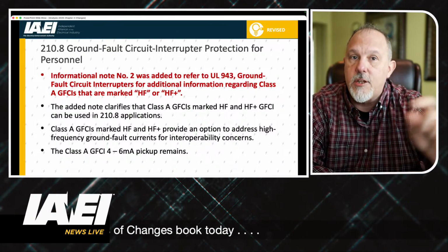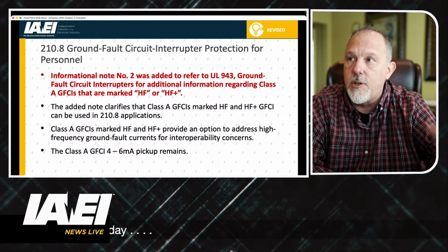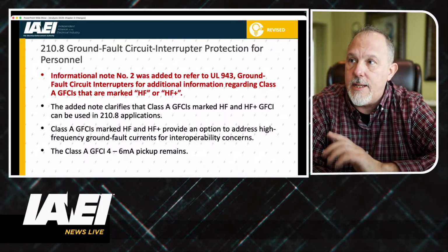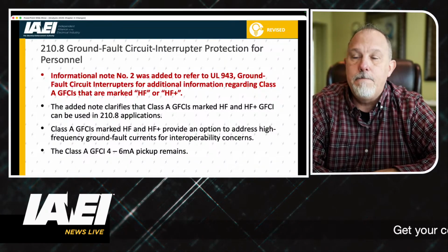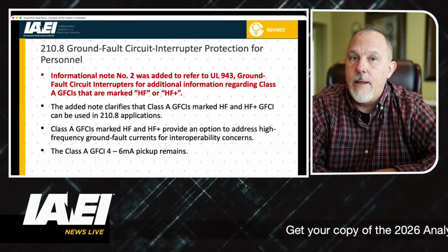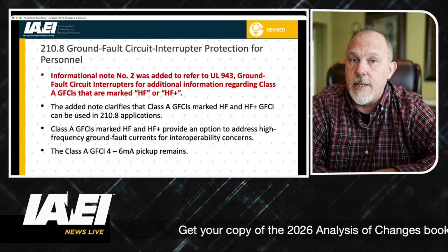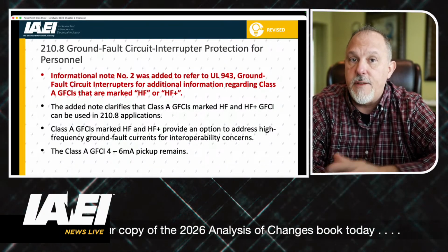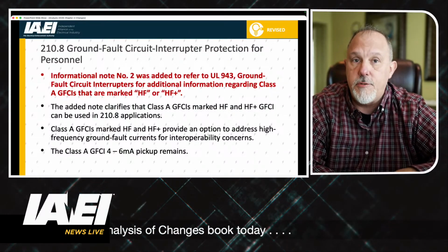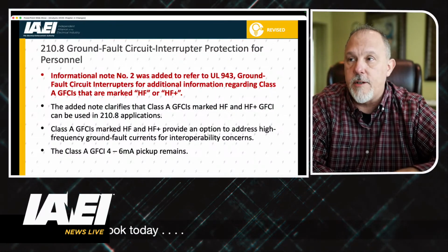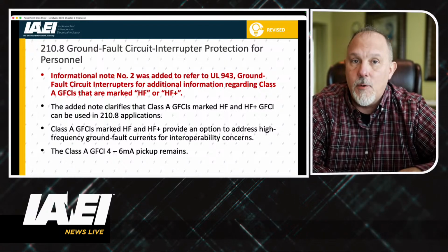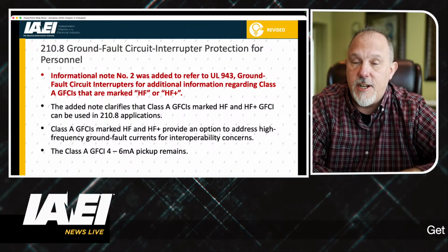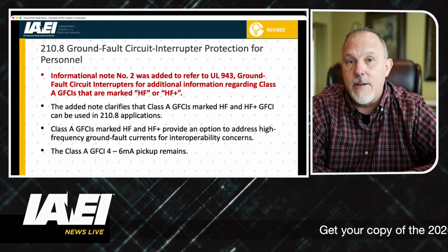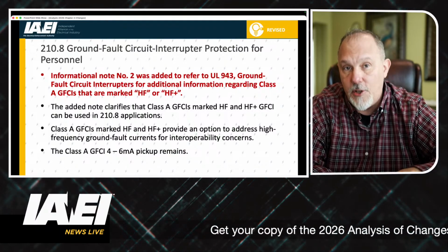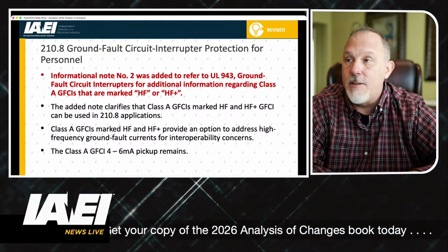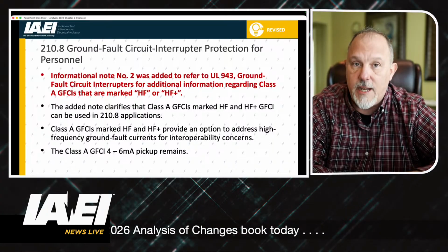When you look at the requirement in the National Electrical Code in 210.8, you'll see that informational note. It doesn't prohibit the installation of a dual-function device, even without that informational note. So it's just an awareness thing, meaning if you're on an earlier edition and you see one out there, it's not a violation of the code. You're allowed to use it. There's no prohibition. It's still a GFCI.